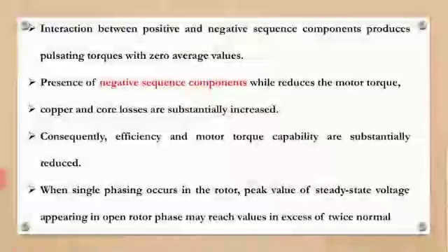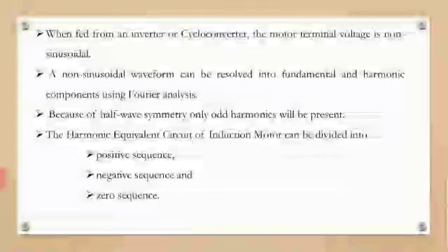Next, the analysis of an induction motor fed from a non-sinusoidal voltage supply. When do we obtain this non-sinusoidal voltage? When the motor is fed from an inverter or cycloconverter. When induction motors are fed from an inverter or cycloconverter, the motor terminal voltage is non-sinusoidal.